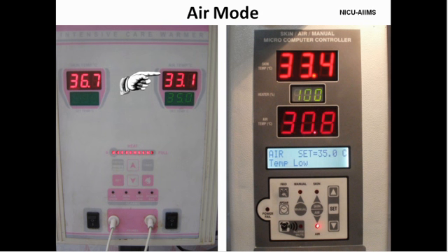What has happened after this? The heater output has automatically increased to 100% for the air temperature to reach the set temperature. A similar situation you can see on the right side. The air temperature set is 35 degrees Celsius. The actual air temperature is 30.8 degrees Celsius and the patient's temperature is 33.4 degrees Celsius. Heater output is 100% and you can also see that the alarm is activated.